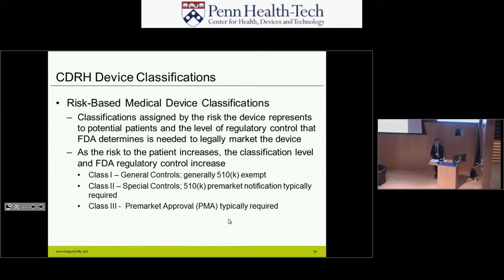The general controls are, you have to register with the FDA as a company. You have to say what devices you're going to be putting out onto the market. You need to list the device so that they're able to track it as well as the person who's putting it out into the marketplace. Quality systems regulations often apply, and those are your manufacturing regulations, and medical device reporting, which basically you need to be reporting when anything bad is happening. Well, not anything bad, but when a life-threatening event occurs or there's a malfunction that could have resulted in a life-threatening event. And these types of things need to be reported to FDA, and everyone does this unless specifically exempted.